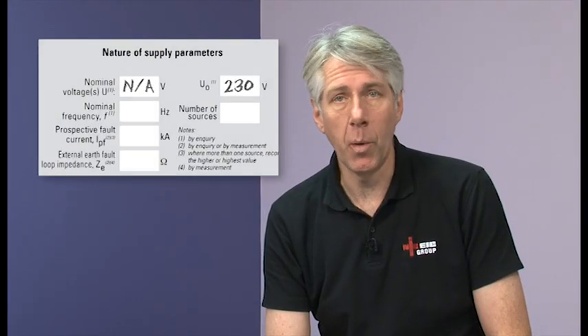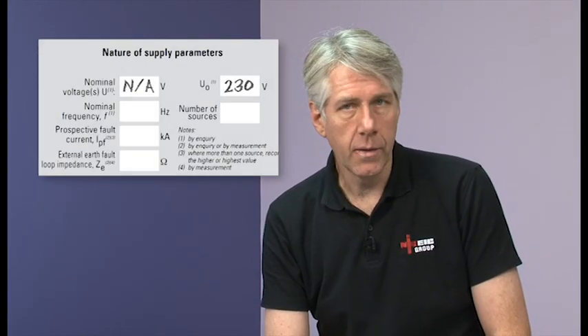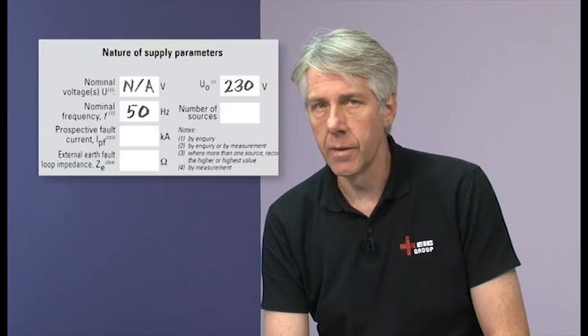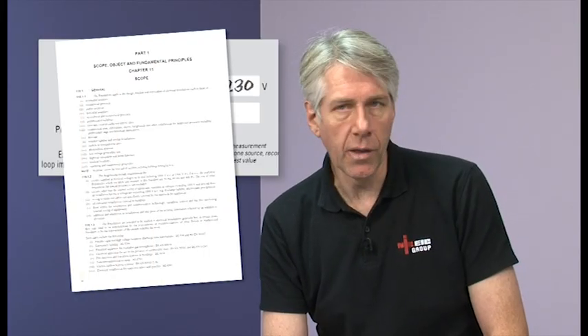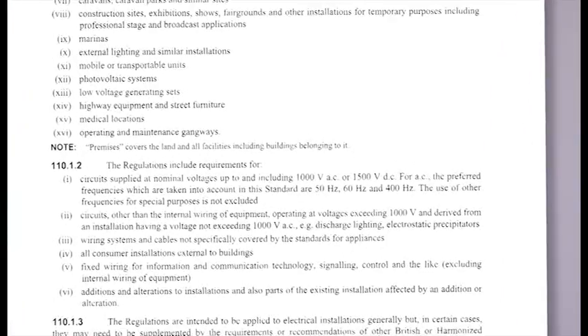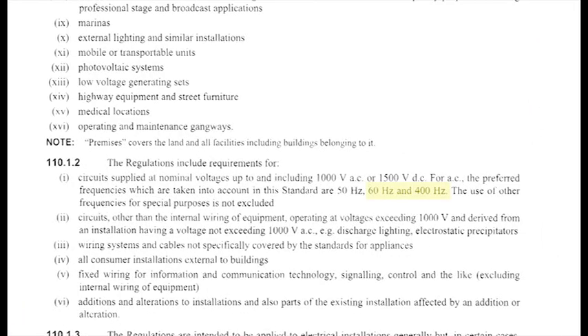Next we have nominal frequency, and again this is a blank box. But in the UK this would typically be 50 Hz. There are preferred frequencies listed in the regs, including 60 Hz and 400 Hz. For example, although rare, you might encounter 60 Hz on American Air Force bases located in the UK.